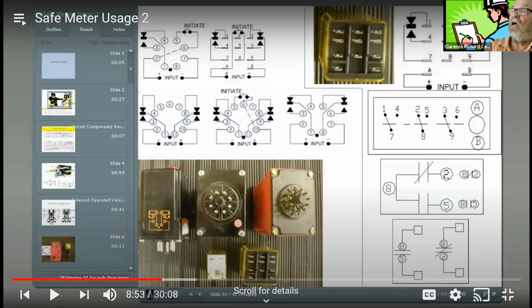This is going to toggle from 3 to 6. And this is going to toggle from 2 to 5. Same thing you have here. This kind of gives it a different look. This here is your single pole double throw. This is your triple pole, double throw. 1 pole, 2 pole, 3 pole. Here's your 9. Here's your 8. Here's your 7 right here. This is your common side. Whenever you energize this, 7 is going to go to 4. 8 is going to go to 5. This 9 right here is going to go to 6 when you energize it.